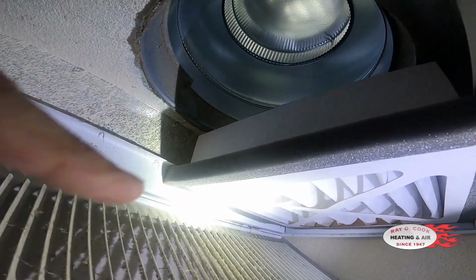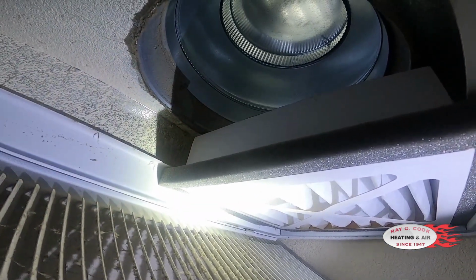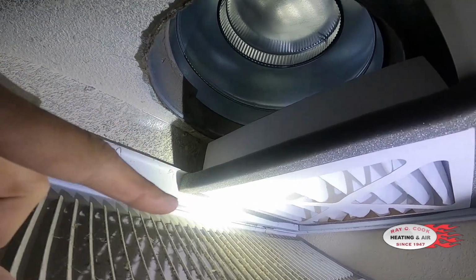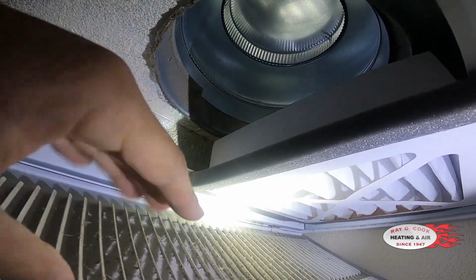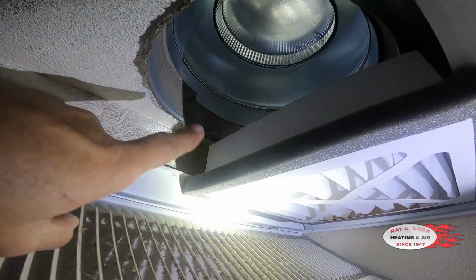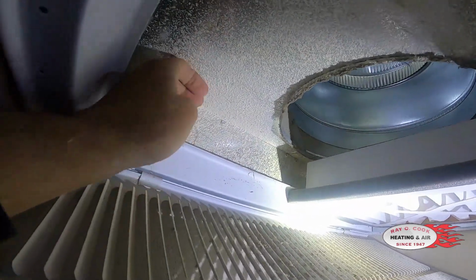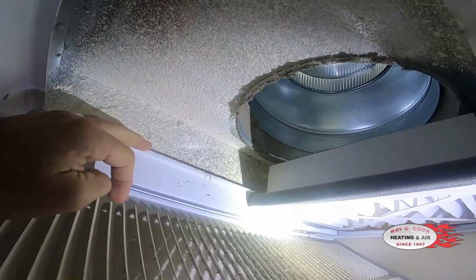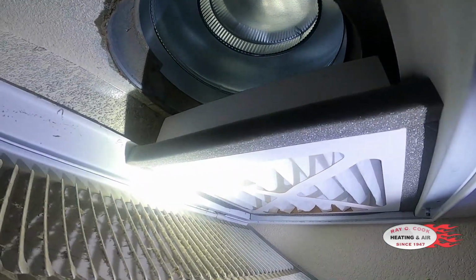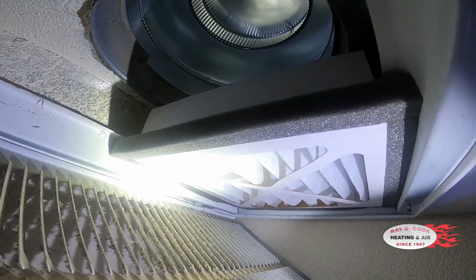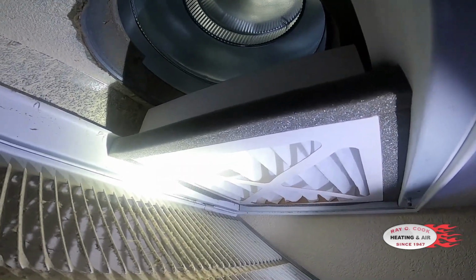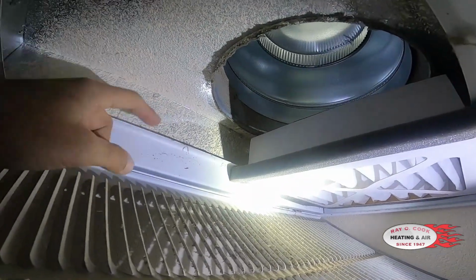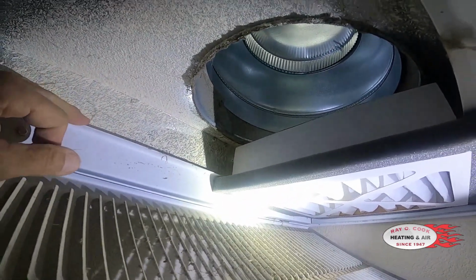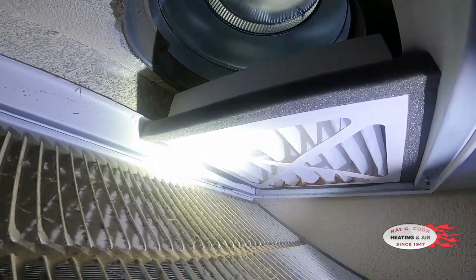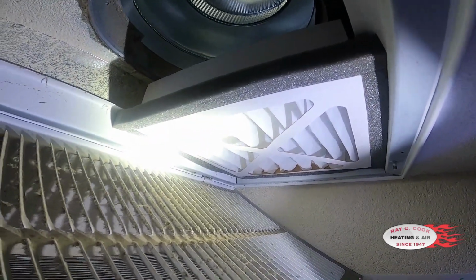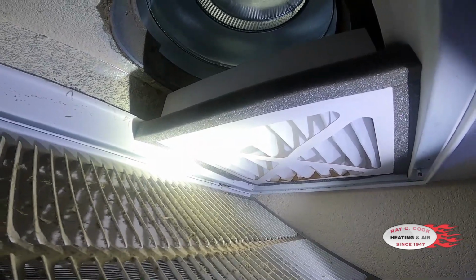And if we put one of these high volume filters, 3-inch filters, in a can like this, it would fit. But the only thing you would filter is the duct. Out here on the edges, the filter would be hitting this shallow box and actually cause more restriction than a lesser quality 1-inch filter. So it's important to understand modification of this box may be needed if you want improved air filtration, and that's just part of doing the air filtration thing correctly.